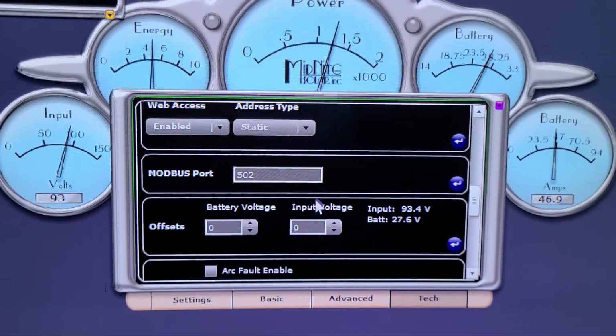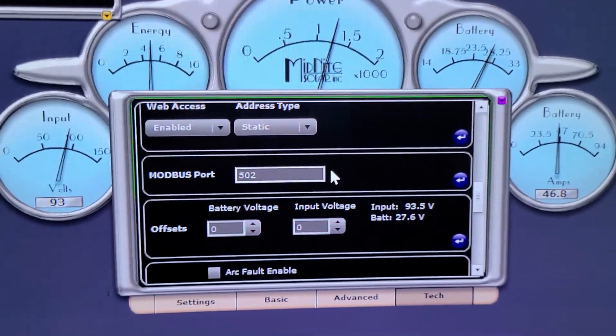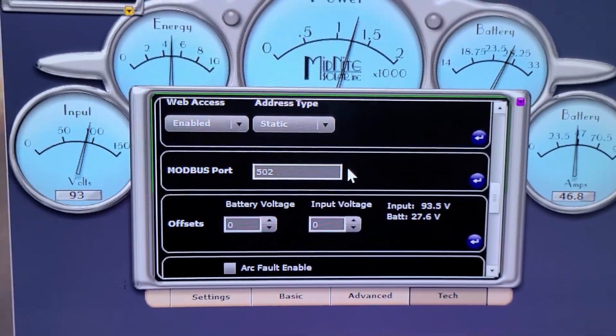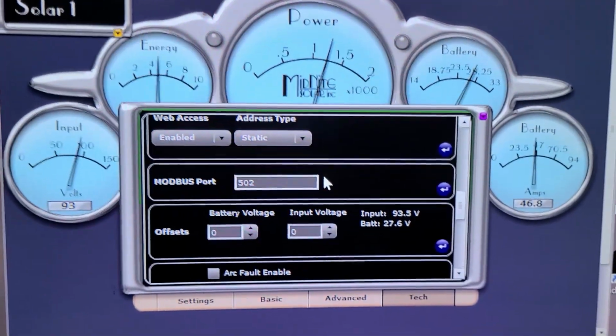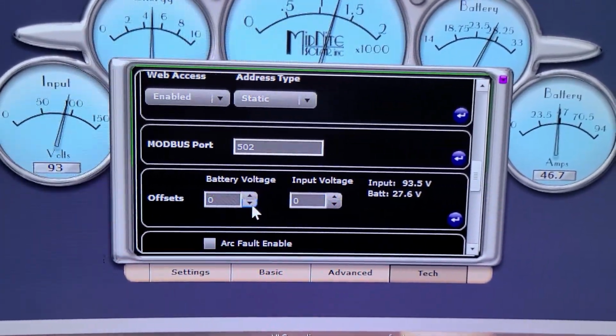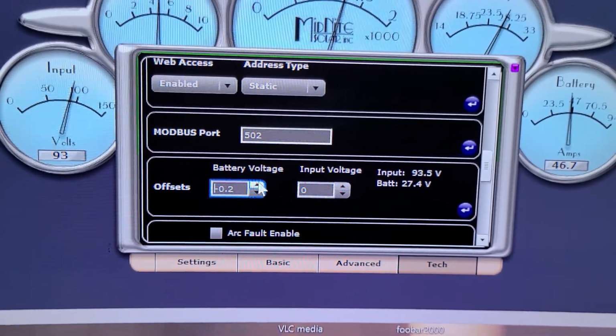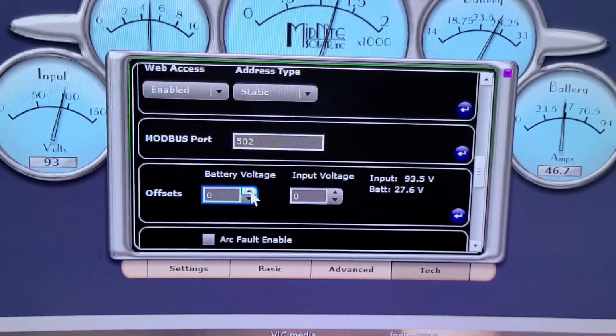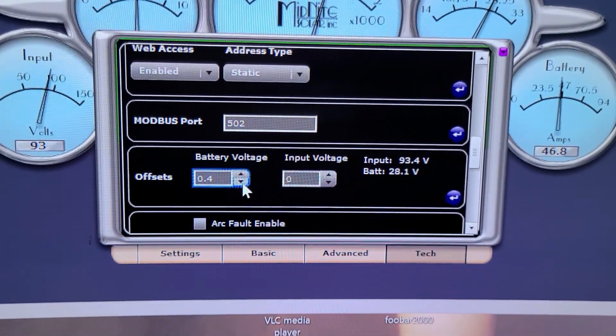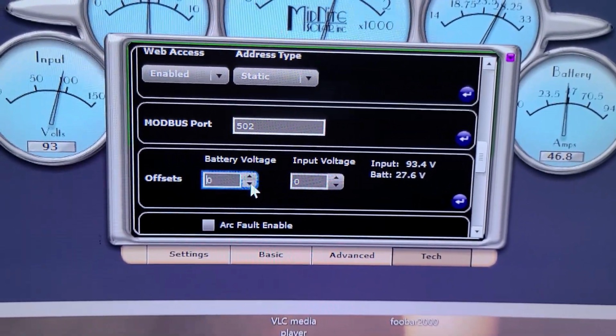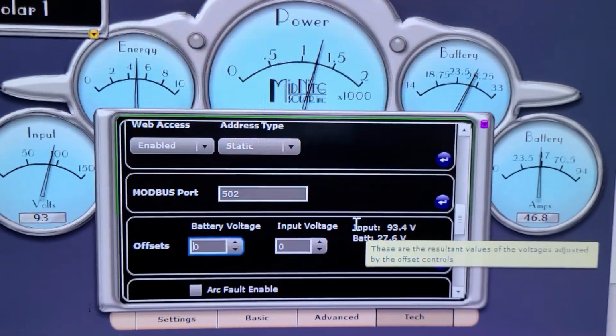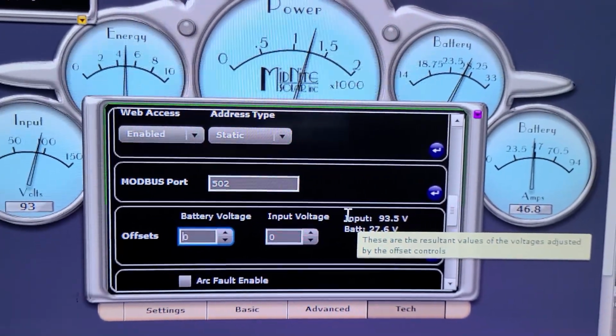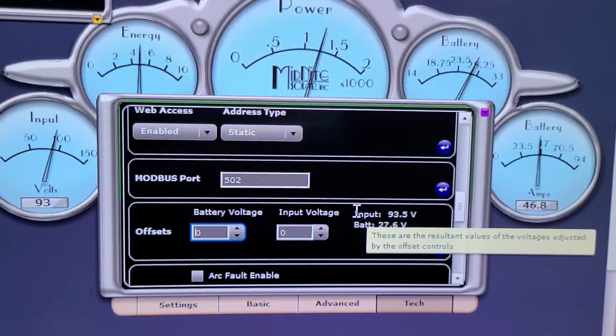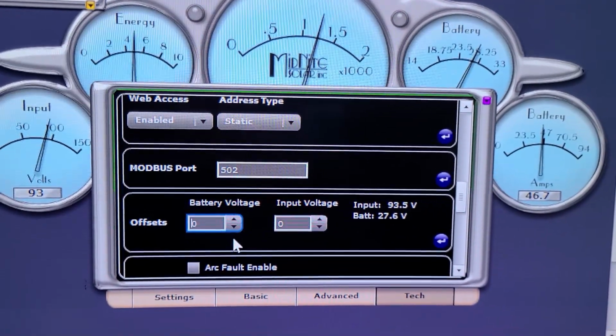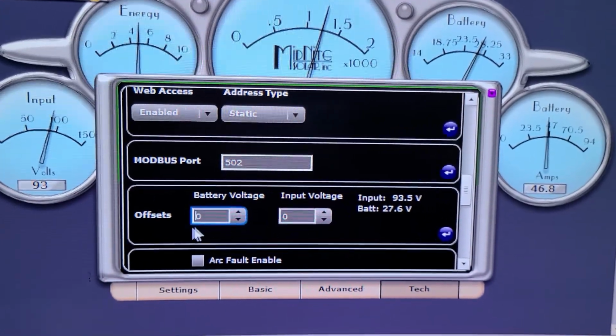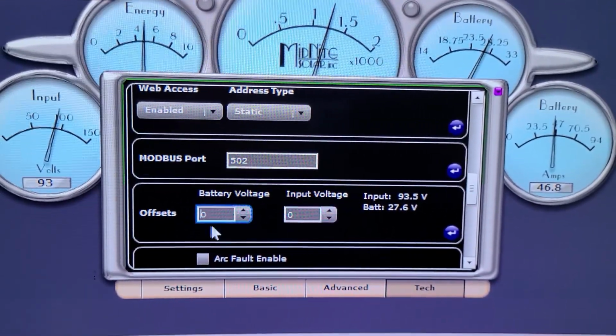Two controllers don't usually have the issue, but when you start having 3 and 4 controllers at a time, you usually have to take this -1 or bump it up a couple volts. Well, we don't need to do that. When you do these tweaks, what you want to do is set your controller's voltage offsets to 0.